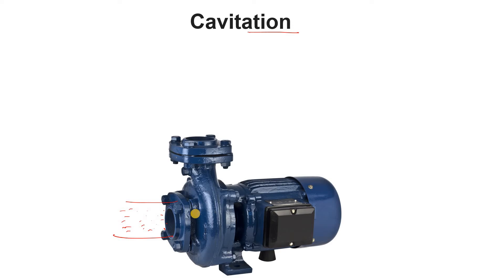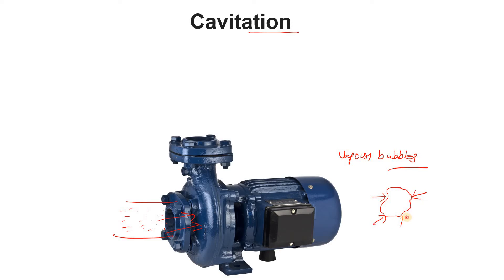When boiling occurs, vapor bubbles form. Those vapor bubbles enter the system through the impeller. In a centrifugal pump, the impeller is the rotating part, and from the casing the pressure increases. When the pressure increases, force is applied on those bubbles and they collapse. The surrounding liquid rushes in to fill that gap, which damages the pump impeller and the casing — that's why cavitation is dangerous for the pump.